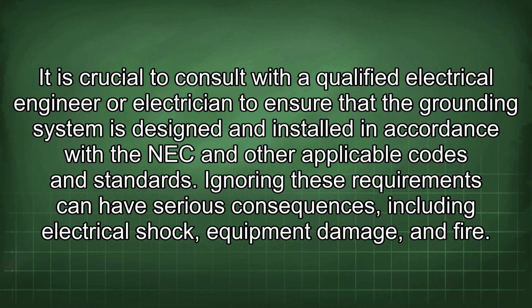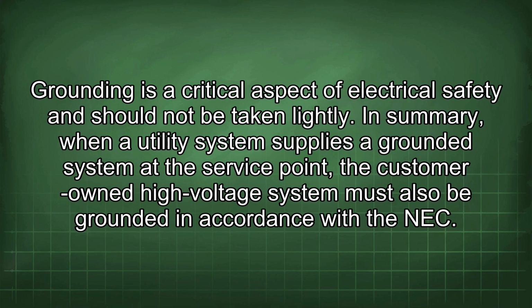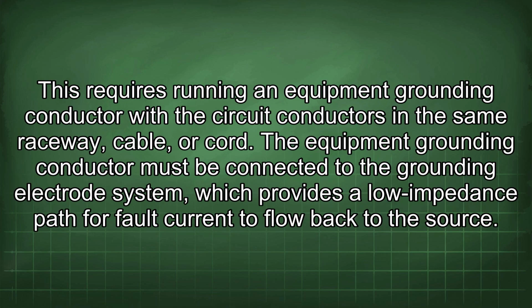Ignoring these requirements can have serious consequences, including electrical shock, equipment damage, and fire. Grounding is a critical aspect of electrical safety and should not be taken lightly. In summary, when a utility system supplies a grounded system at the service point, the customer-owned high-voltage system must also be grounded in accordance with the NEC. This requires running an equipment grounding conductor with the circuit conductors in the same raceway, cable, or cord. The equipment grounding conductor must be connected to the grounding electrode system, which provides a low impedance path for fault current to flow back to the source.